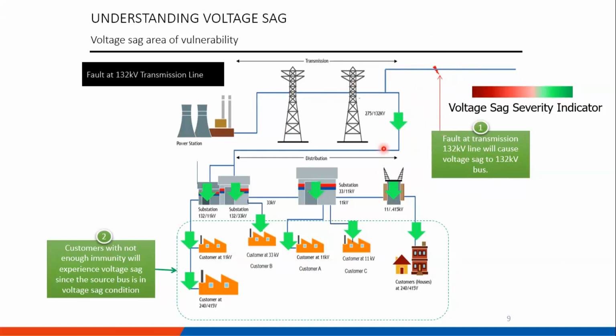It's still in the green zone, and it will affect all the connected substations. So you can see a substation here, a substation here, and then any customer that doesn't have enough immunity will also be affected. However, it's not as severe as the previous example. Most customers are still in the green zone because of the distance of the fault. So it's advisable for customers with sensitive equipment to have enough immunity to ride through any voltage sag that happens. We will share that later.